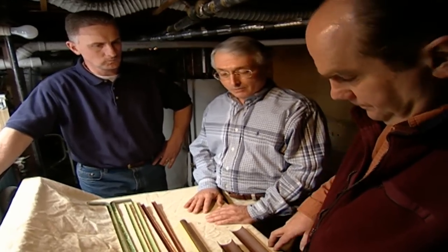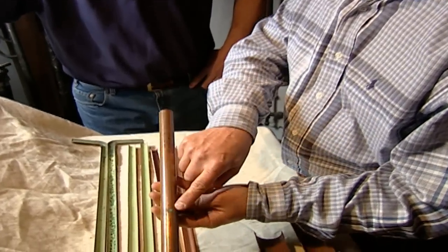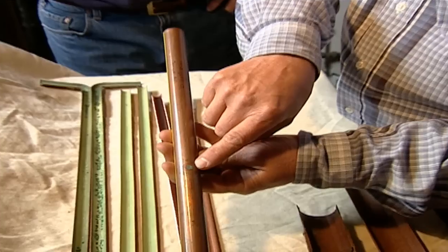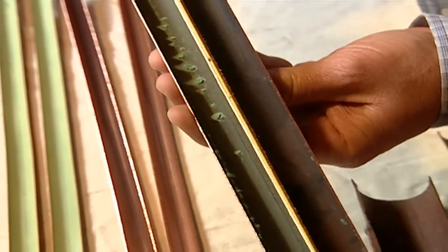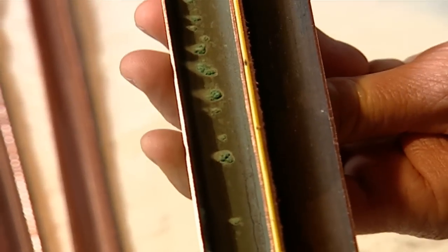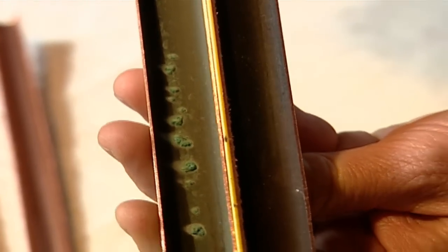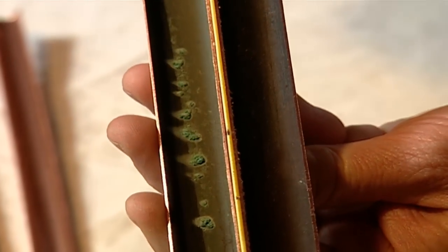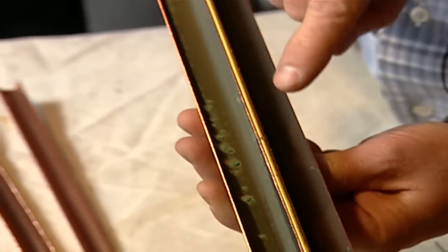Like what? Well, one example is stagnation. Here is a piece of pipe in which we observe the corrosion product on the outside due to a leak. When we split the pipe and examine the inside, we see rows of pits. What happened in this case is the new pipe was installed and it was initially flush, but then it was allowed to remain stagnant for an extended period of time, several months. And right at the water line, inside the pipe, we have rows of pits.